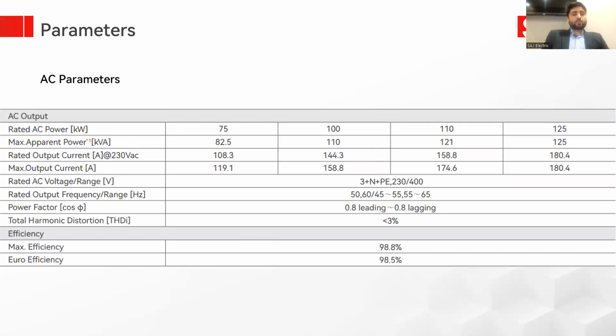AC parameters. The rated AC power is 75 kilowatt for the 75 kilowatt inverters and 125 kilowatt for the 125 kilowatt inverters. Now in Pakistan, the 100 and 125 kilowatt inverters are available with our distributors. Maximum apparent power is 82.5, 110, 121, and 125. The rated AC voltage is three phase. The frequency is 50 to 65 hertz. Power factor is 0.8 leading to 0.8 lagging. Total harmonic distortion is less than 3%. Maximum efficiency is 98.8% and the Euro efficiency is 98.5%.